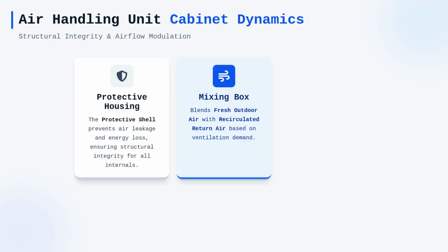The housing of an air handling unit serves as the protective shell for all internal components, and its structural integrity is paramount to preventing air leakage and energy loss. Inside this cabinet, the mixing box plays a critical role by blending recirculated return air with fresh outdoor air in specific ratios determined by the building's demand for ventilation.